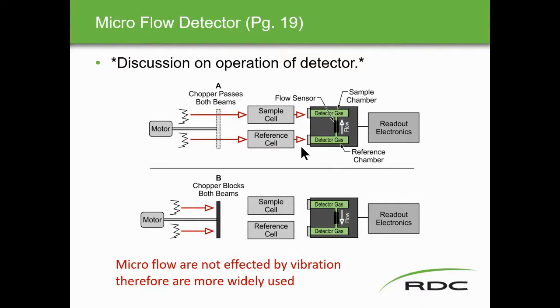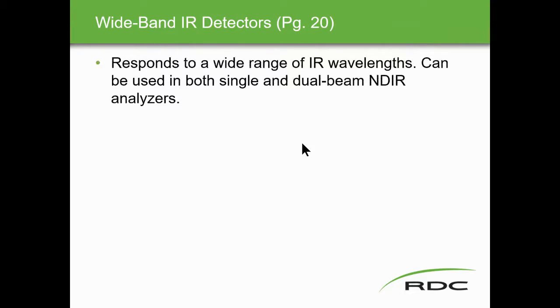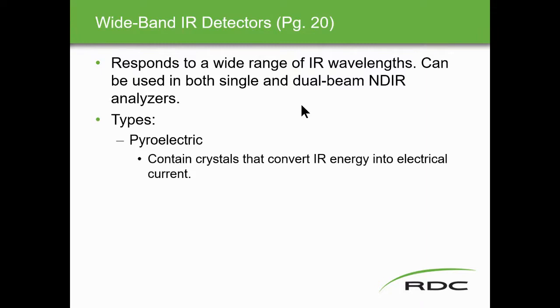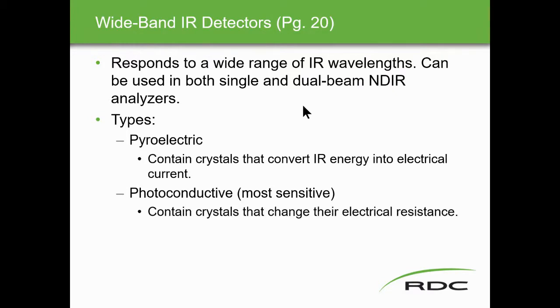Microflow detectors are not affected by vibration, so they are more widely used in plant environments compared to Luft detectors, which can be affected by vibration. Wideband IR detectors respond to a wide range of IR wavelengths and can be used in both single and dual beam NDIR analyzers. Types include pyroelectric detectors, which contain crystals that convert IR energy into electrical current, and photoconductive detectors, which are the most sensitive and contain crystals that change their electrical resistance.